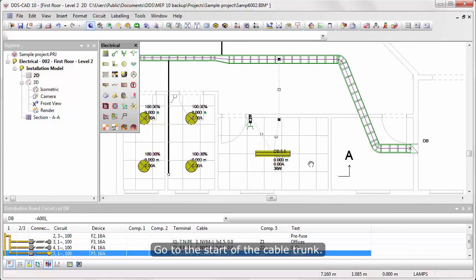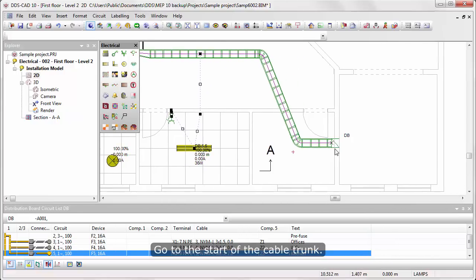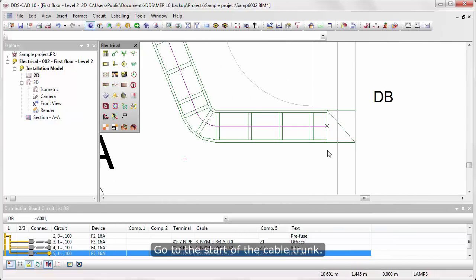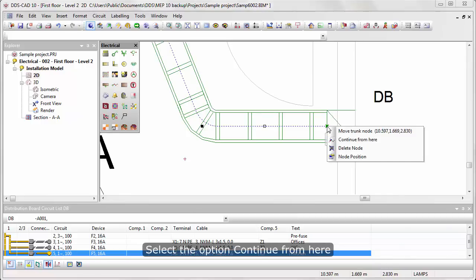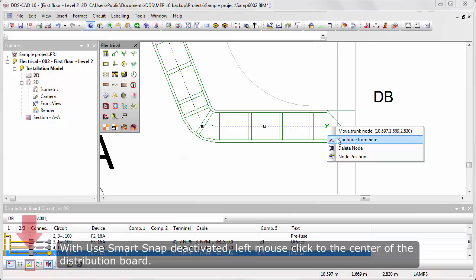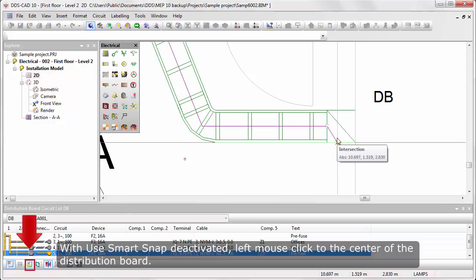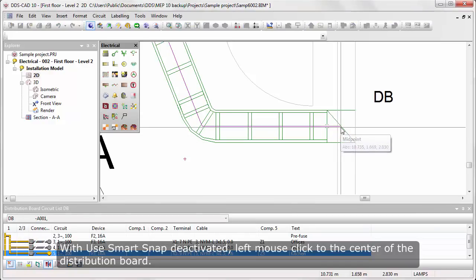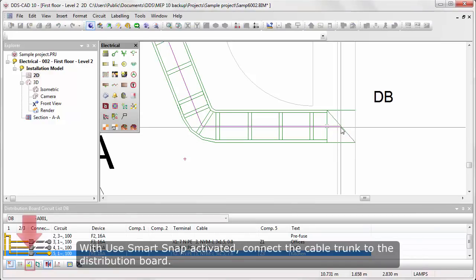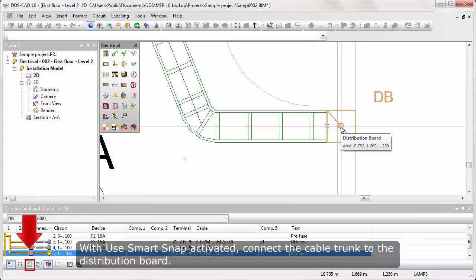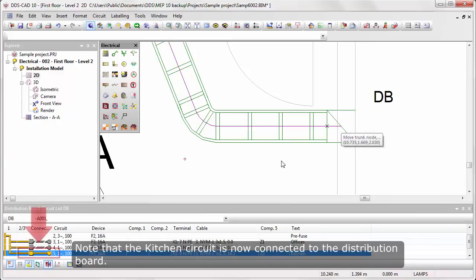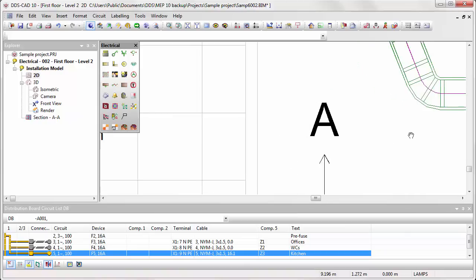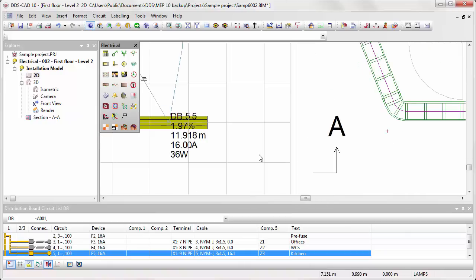Go to the start of the cable trunk. Select the cable trunk, then right mouse click on the Start Node. Select the option Continue from here. With Use Smart Snaps deactivated, left mouse click to the center of the distribution board. With Use Smart Snaps activated, connect the cable trunk to the distribution board. Note that the Kitchen circuit is now connected to the distribution board.